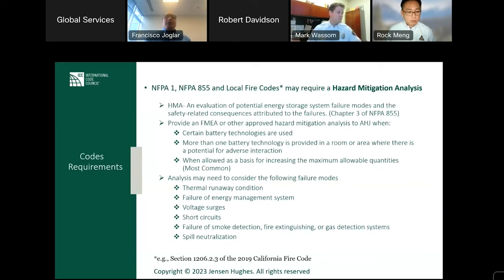All right, so a hazard mitigation analysis, we hear the term HMA, and we hear the term FMEA, which is failure modes and effects analysis. So this is where I see sometimes some confusion. So FMEA is a reliability tool that manufacturers use and people in process safety use to identify failure modes of systems. In the context of fire safety, we have interpreted it to be, let's identify what are the potential causes for a thermal runaway, right? So we limit the scope of an FMEA that could look for failure modes of system operation, what if the system fails, etc. But this doesn't lead to fire accidents. We kind of keep them out of the scope.